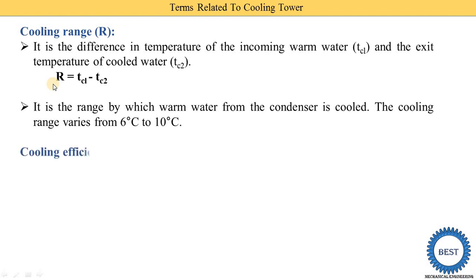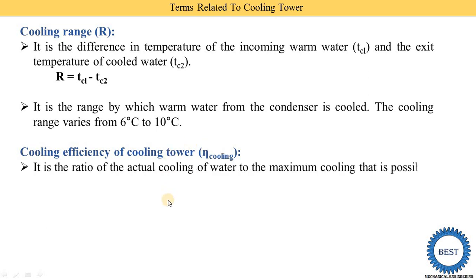The next point is the cooling efficiency of the cooling tower. It is the ratio of the actual cooling of water to the maximum cooling that is possible. The actual cooling is the inlet temperature of the warm water minus the outlet temperature (TC1 − TC2). The maximum cooling possible is TC1 − TWB, where TWB is the wet bulb temperature. So cooling efficiency = (TC1 − TC2) / (TC1 − TWB). This is called the cooling efficiency of the cooling tower.